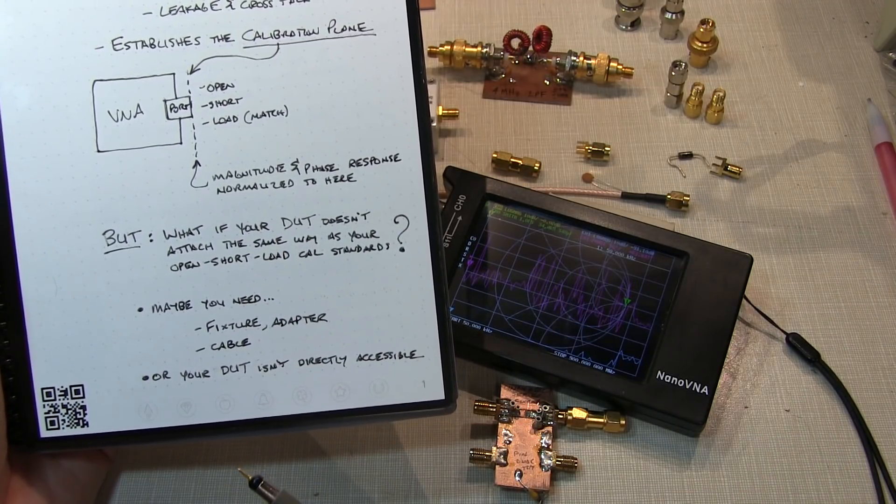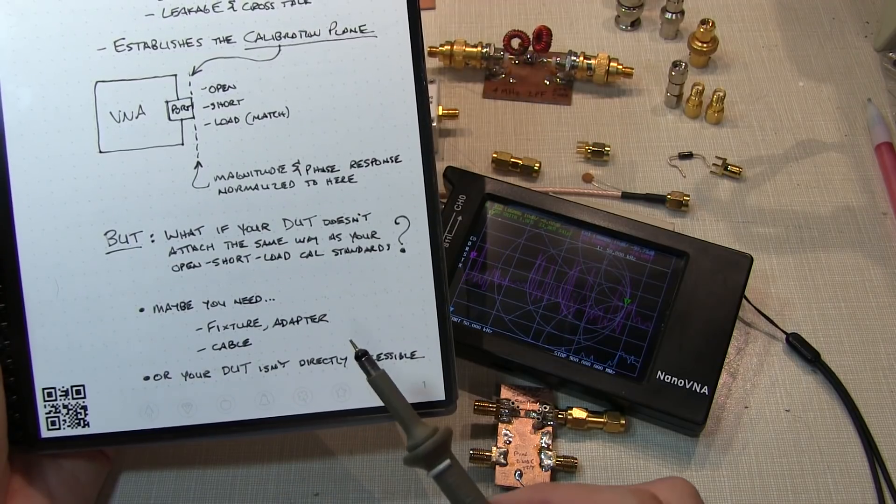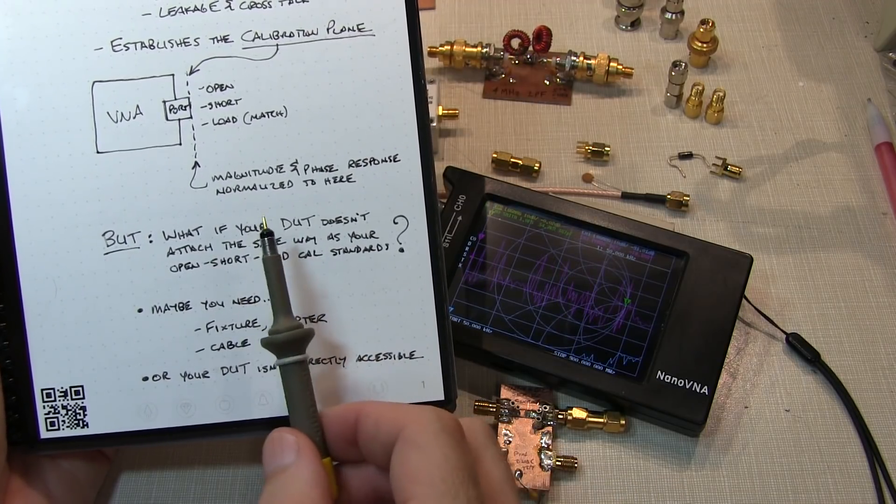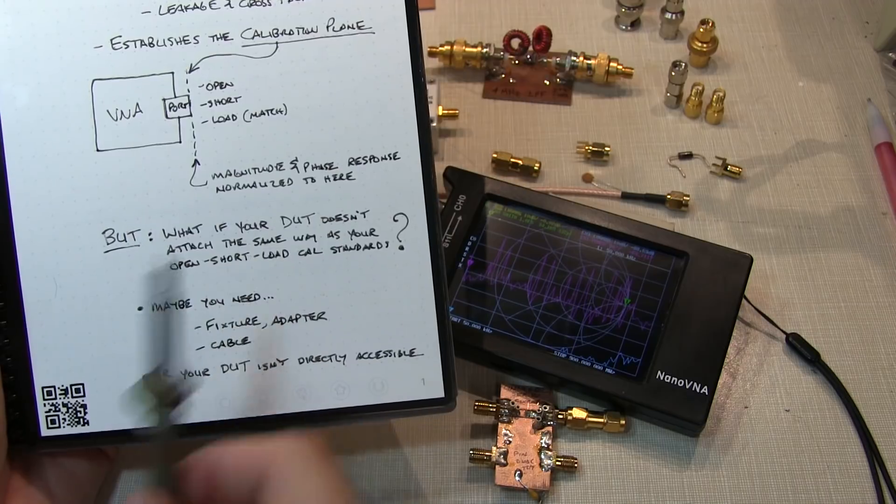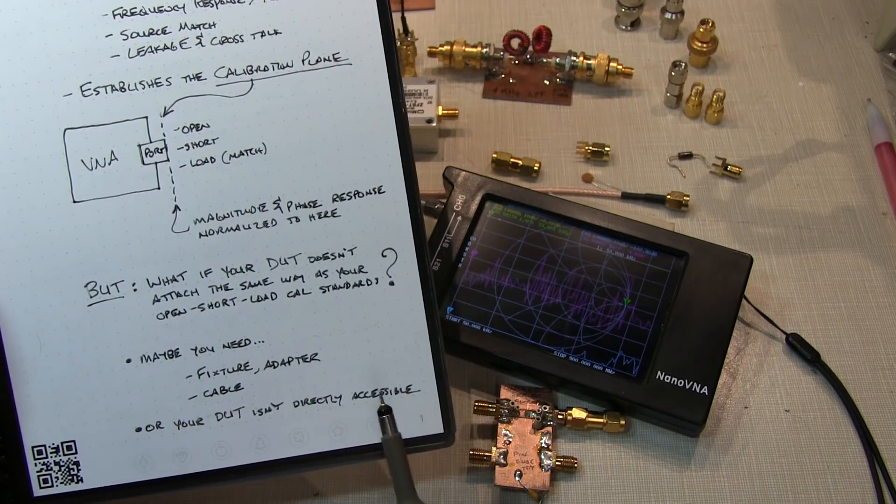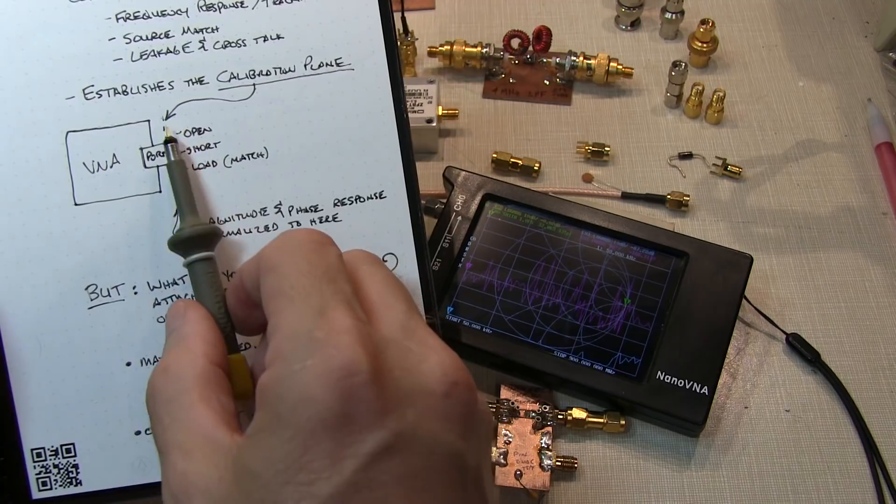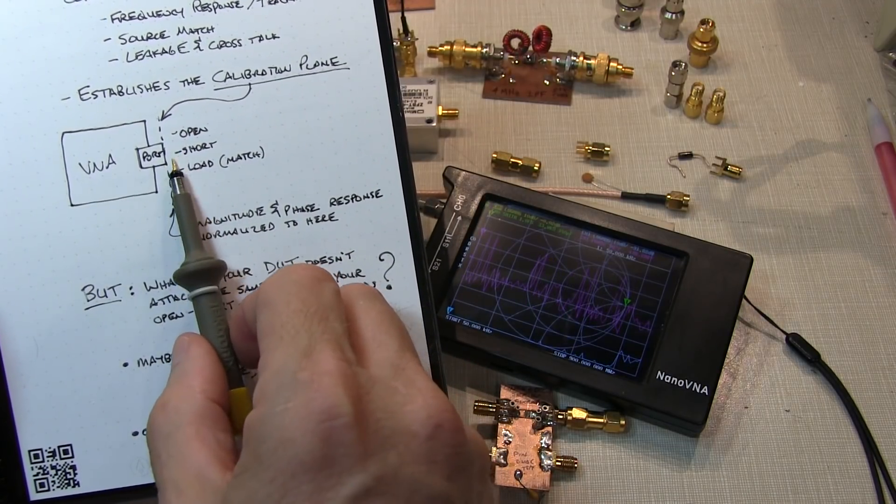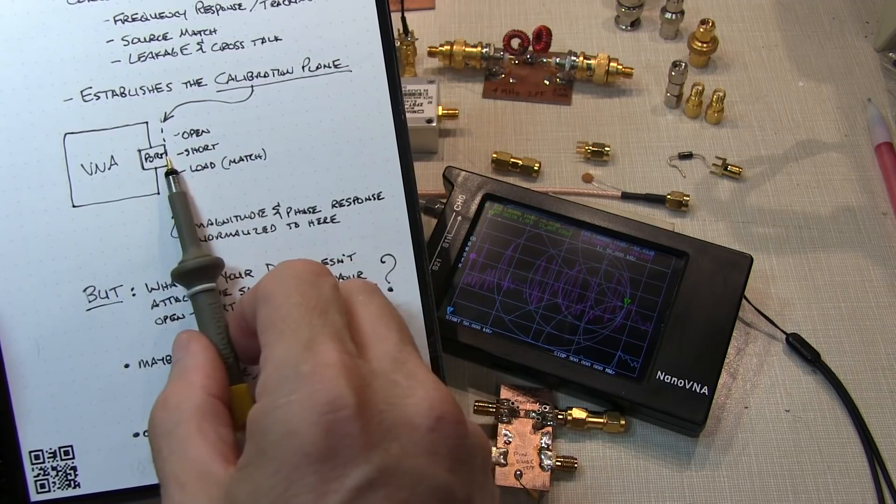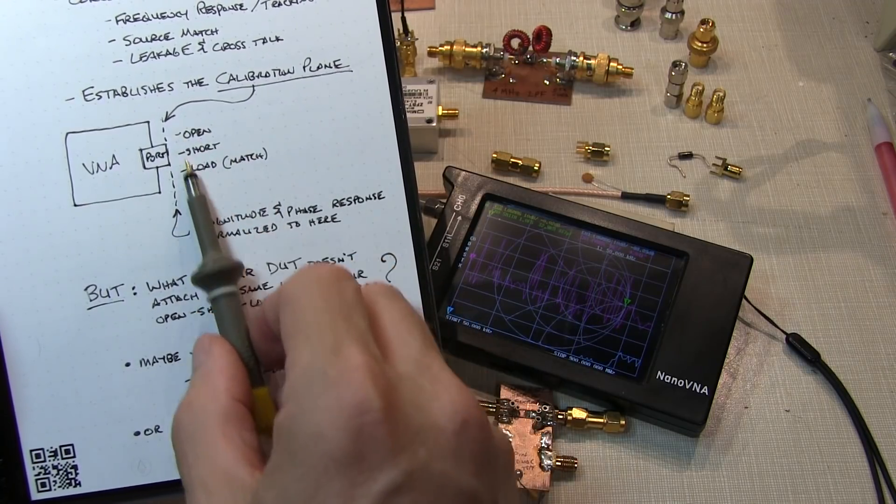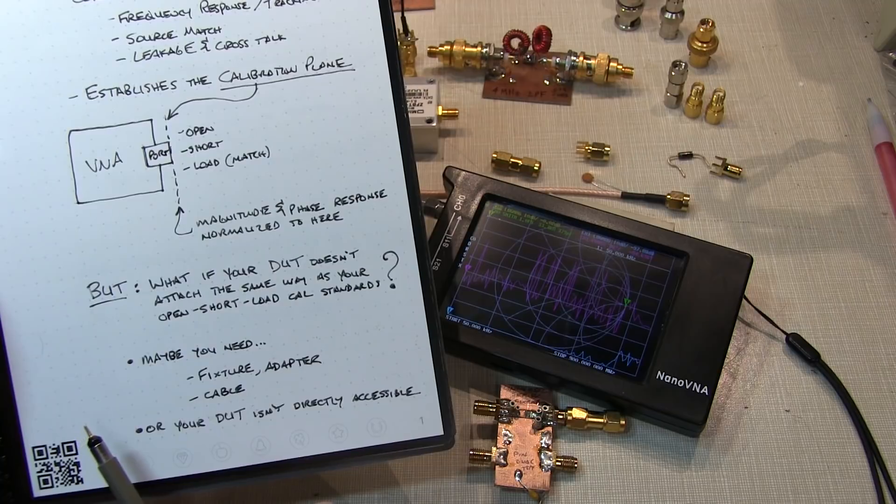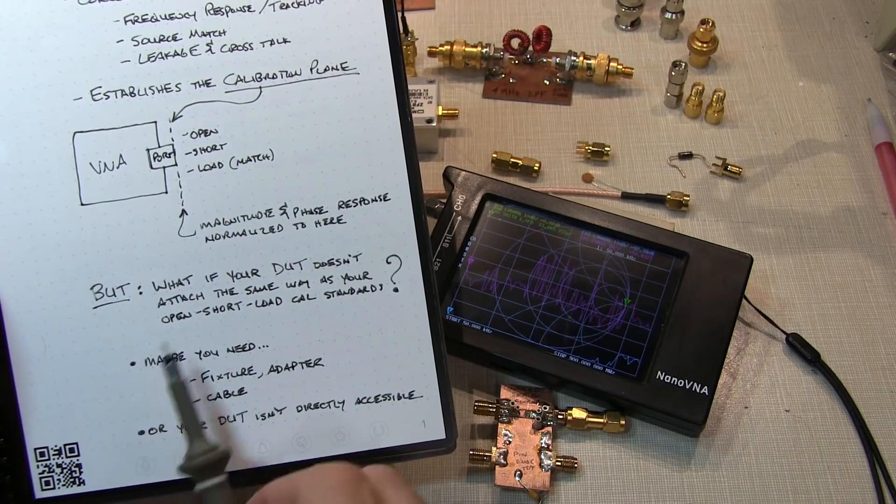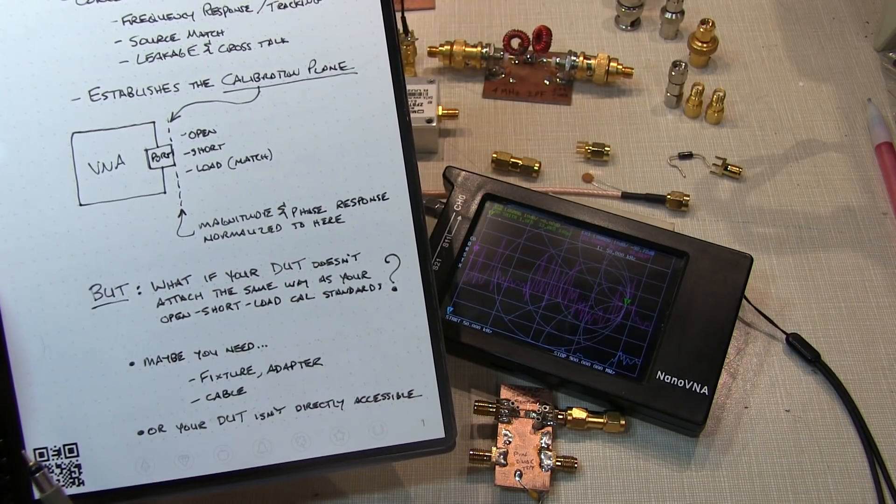Well, this actually could present a problem, potentially, if you want to accurately measure the complex impedance looking into your device. The reason for this is that each of these devices that you add to the VNA port beyond where you made your calibration will add an additional delay or phase shift compared to where that calibration was done. And that is essentially going to alter the impedance that is seen by the VNA.